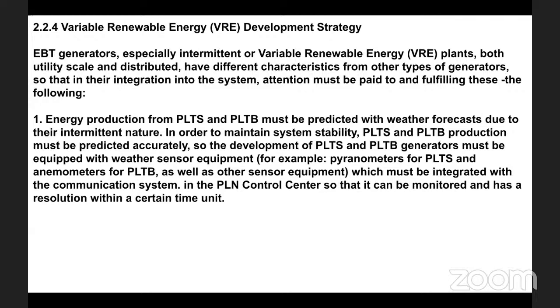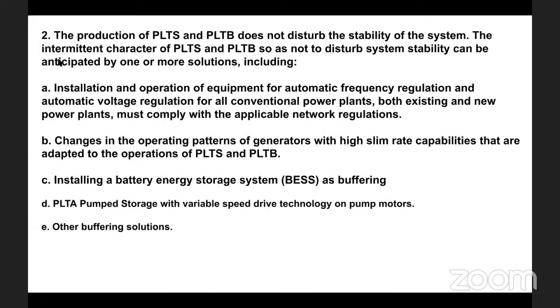In order to maintain system stability, PLTS and PLTB production must be predicted accurately, so the development of PLTS and PLTB generators must be equipped with weather sensor equipment, for example pyranometers for PLTS and anemometers for PLTB, as well as other sensor equipment, which must be integrated with the communication system in the PLN control center so that it can be monitored and has a resolution within a certain time unit. Second, the production of PLTS and PLTB must not disturb the stability of the system.